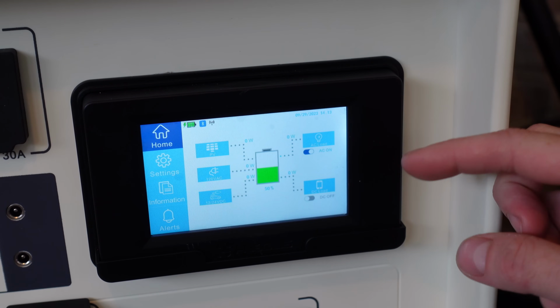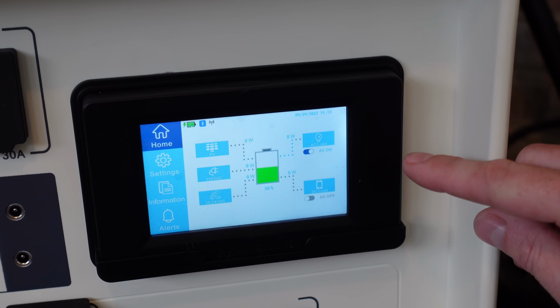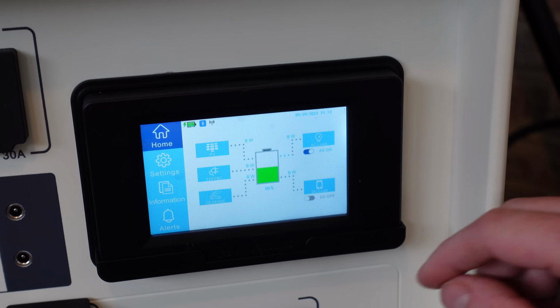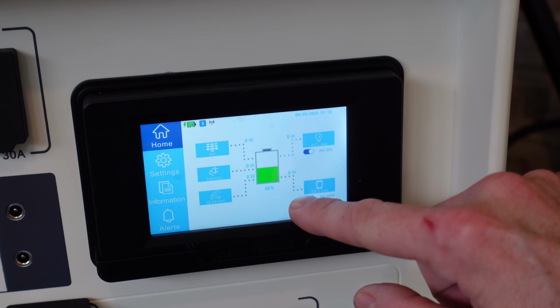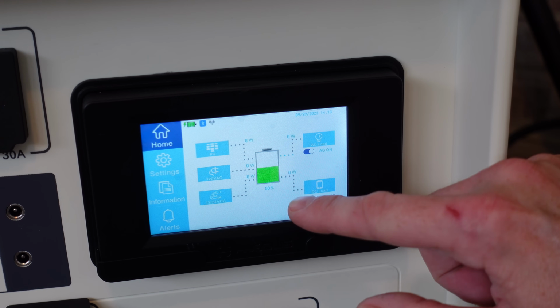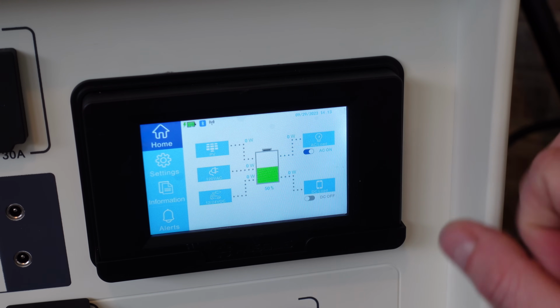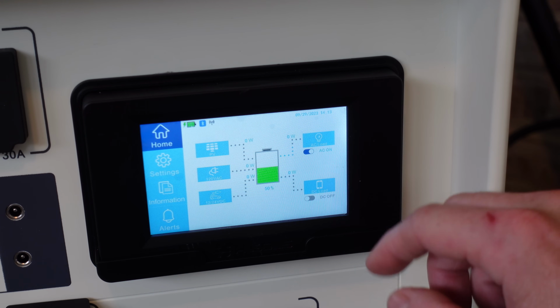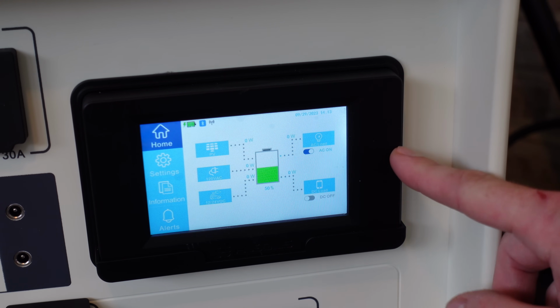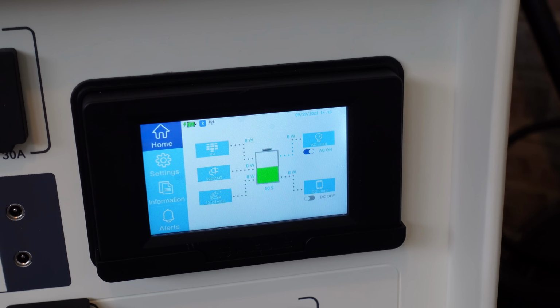So that was actually quite interesting. It actually ran all 3 of those loads until the air compressor reached its maximum pressure and the battery symbol was blinking. So perhaps that was the surge capacity it's rated for, but we do want to make sure this does shut down when it does reach its rated limits. So we're going to try that again here just to see what happens.